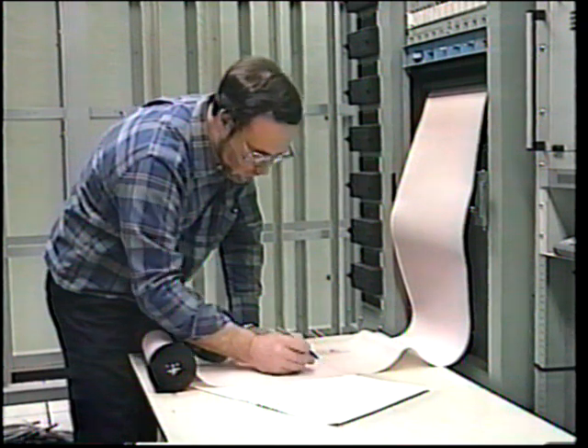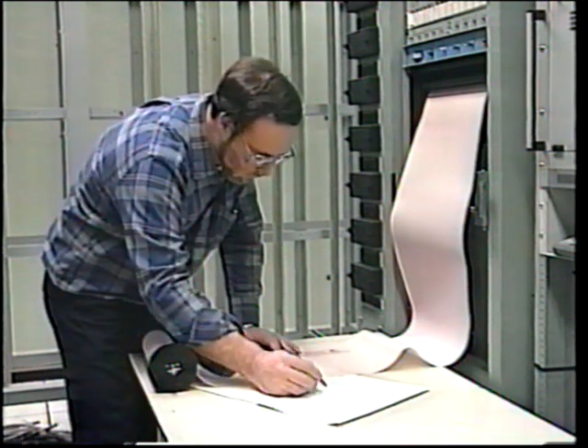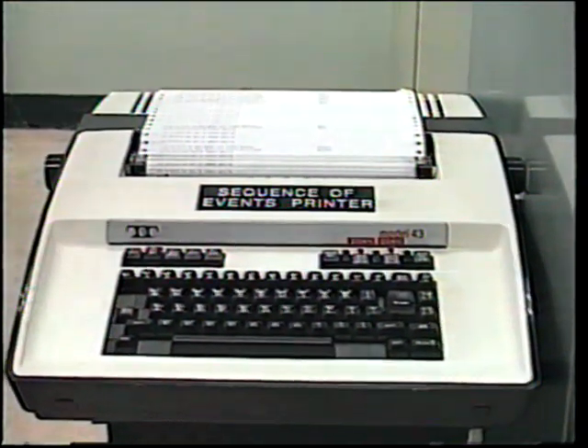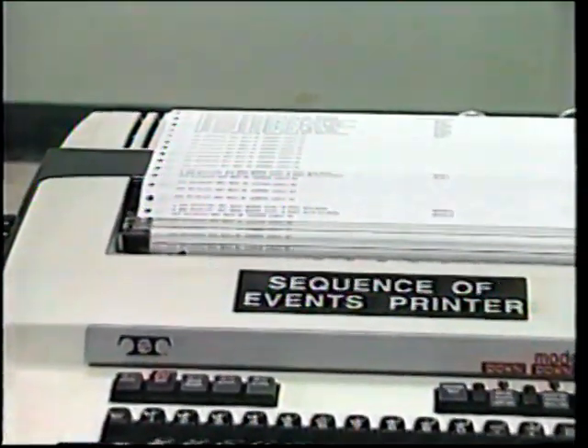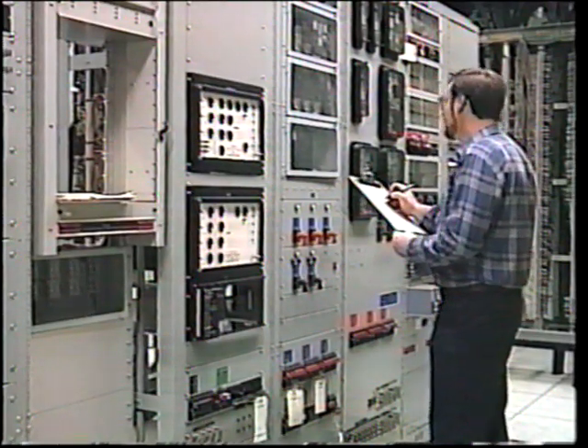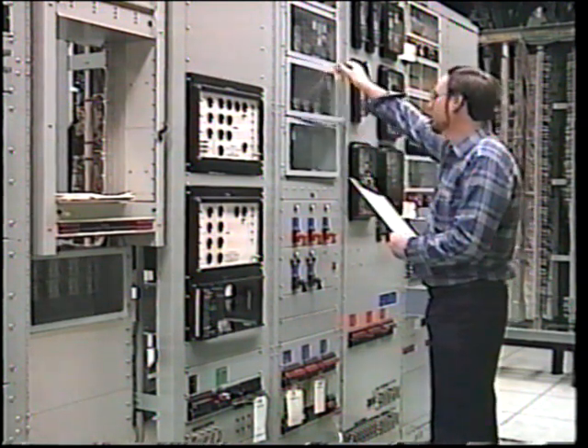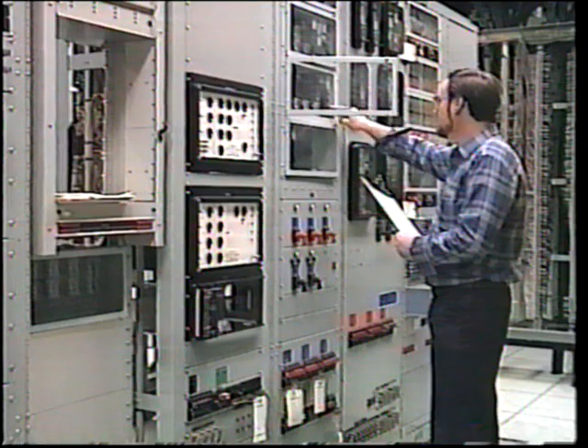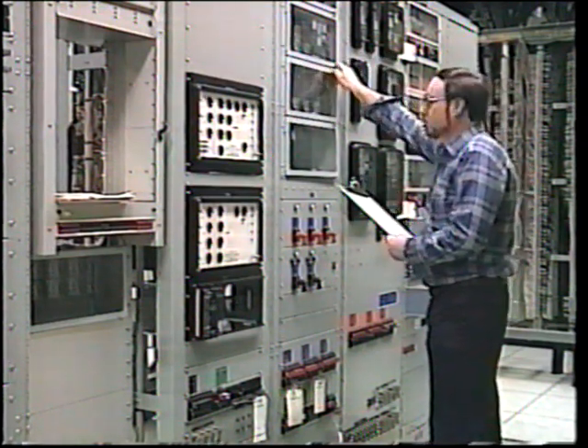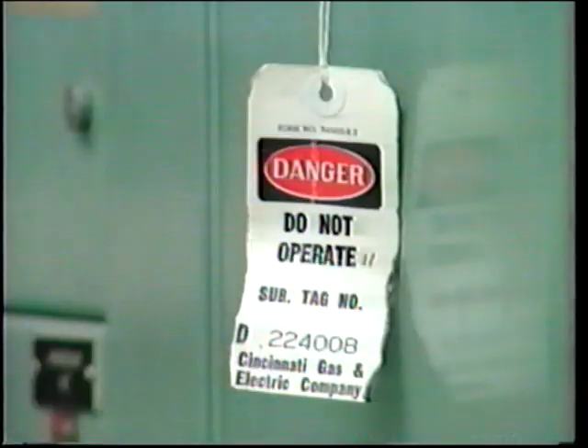When investigating the cause of the problem, it is most useful to go through station oscillograph records and the printout from the events recorder. It may even be necessary to collect and view the records from other substations around the system. On completion of the investigation, all relay targets, annunciators, and alarms must be reset, all test equipment removed, and the equipment returned to as normal condition. If items need to remain isolated due to defect, then this equipment must be properly tagged and the appropriate departments notified. Let's look at a few case histories of misoperation that resulted in a trouble call to relay technicians.